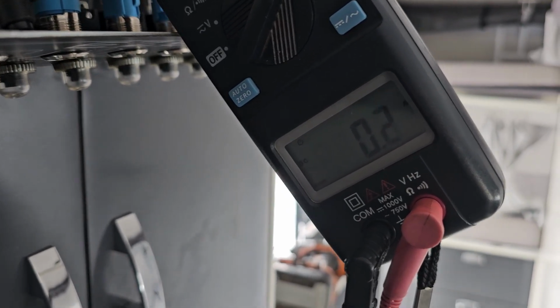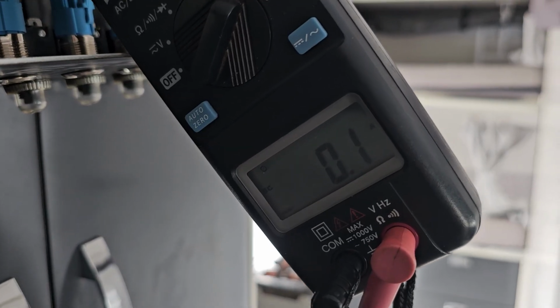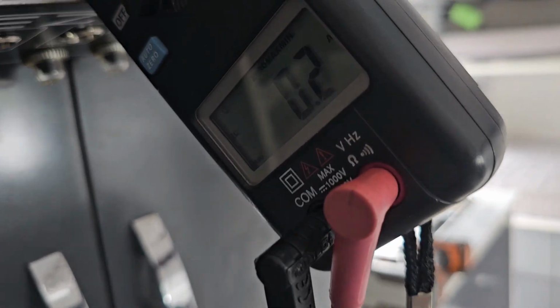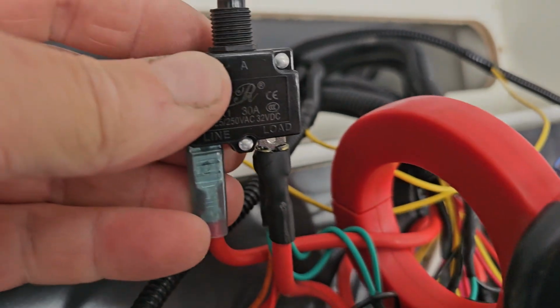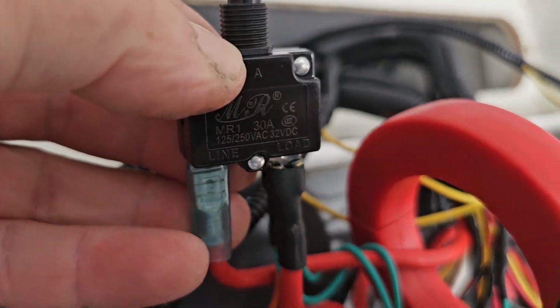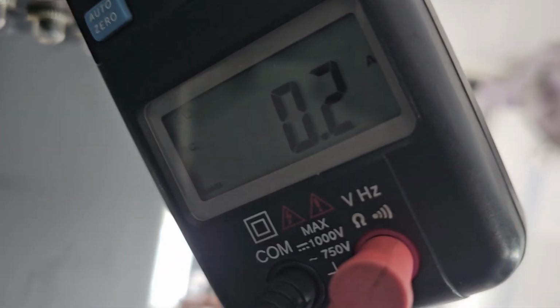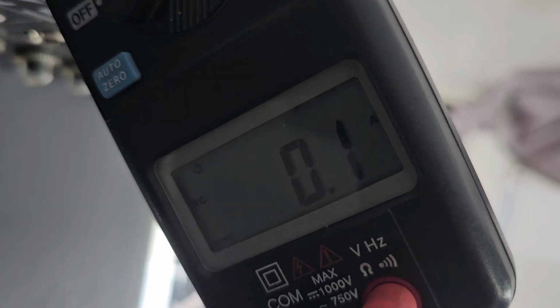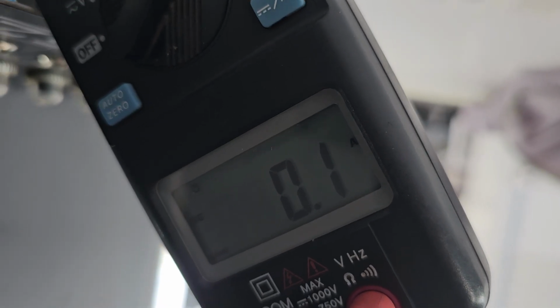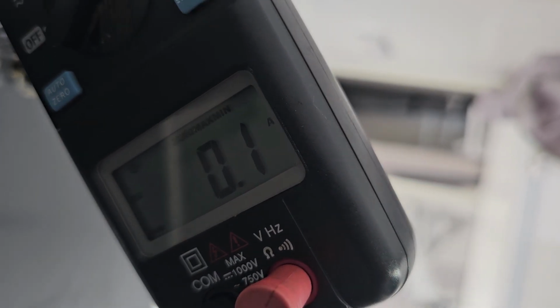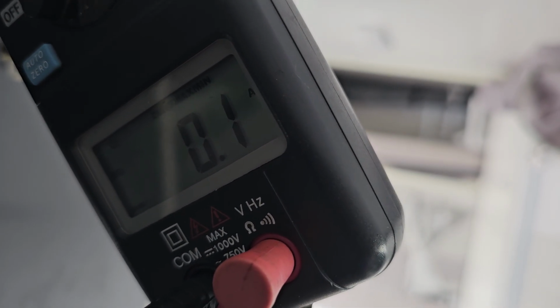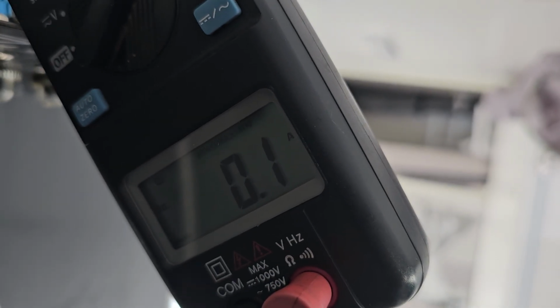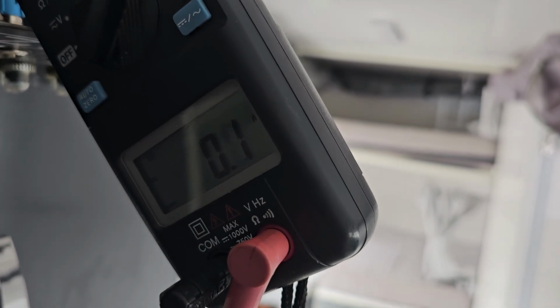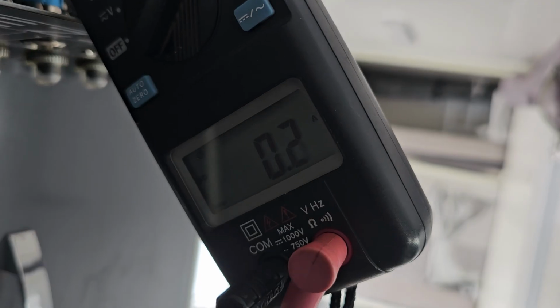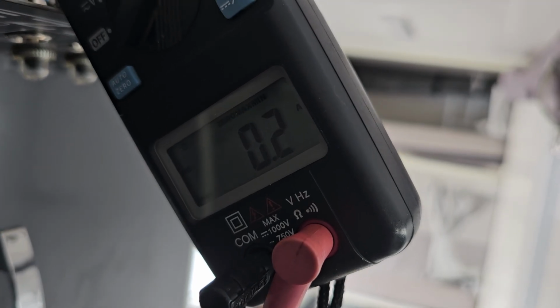Alright, in typical fashion, this hasn't popped. So what I've done, you can now see the 30 amp circuit breaker. I've set this current clamp to minimum maximum, so I'm going to turn the loads on because I've got other things to do, and in theory hopefully minimum maximum will record the maximum current at which it dropped out.